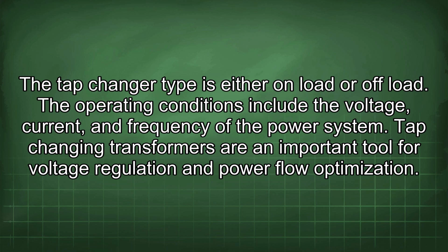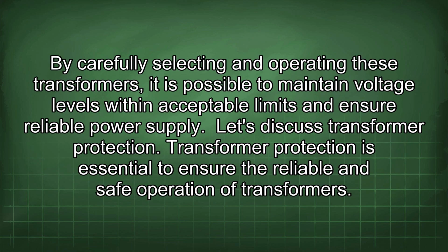Tap-changing transformers are an important tool for voltage regulation and power flow optimization. By carefully selecting and operating these transformers, it is possible to maintain voltage levels within acceptable limits and ensure reliable power supply. Let's discuss transformer protection.